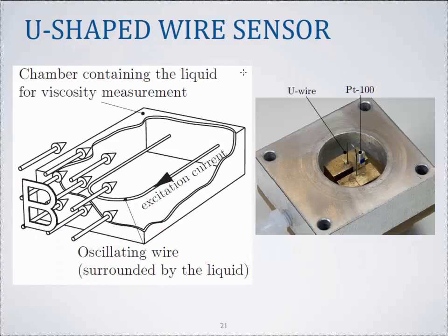The U-shaped wire carries alternating currents and the wire is placed in an outer magnetic field so it starts oscillating in this direction, which in turn induces a voltage on the tip of the resonator which we take as measure for reading out our viscosity sensor.